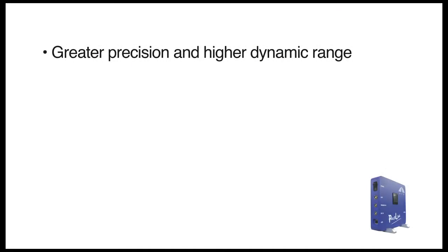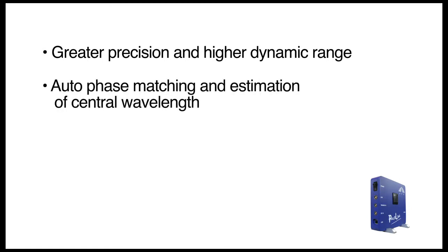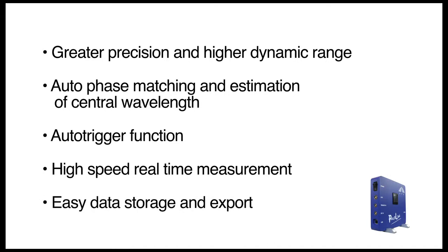Some of the key advantages are greater precision and a higher dynamic range due to the increased resolution of delay and intensity, autophase matching and estimation of the central wavelength, autotrigger that detects a valid trigger signal and measures the trigger frequency, high-speed real-time measurement, thanks to a USB interface, and easy data storage and export.